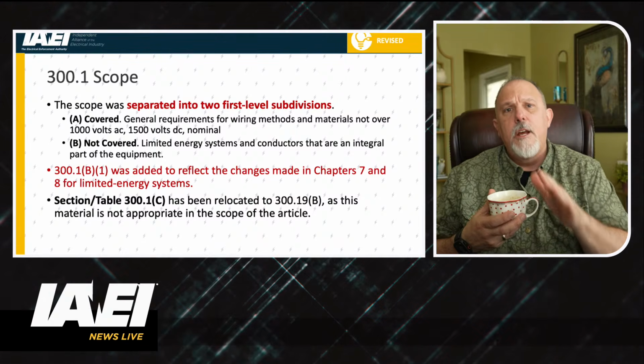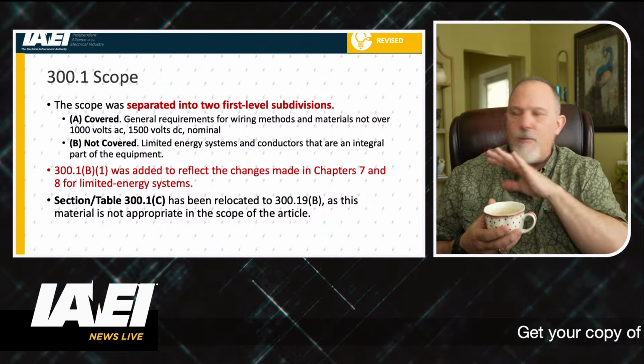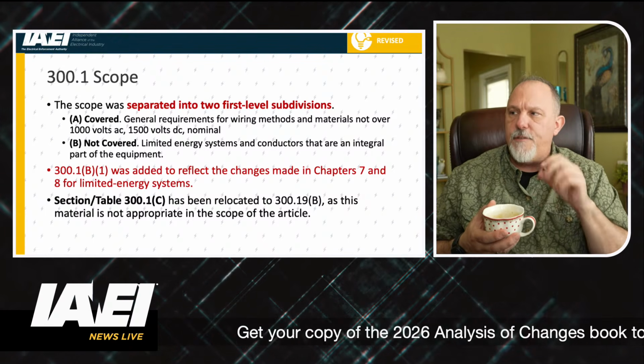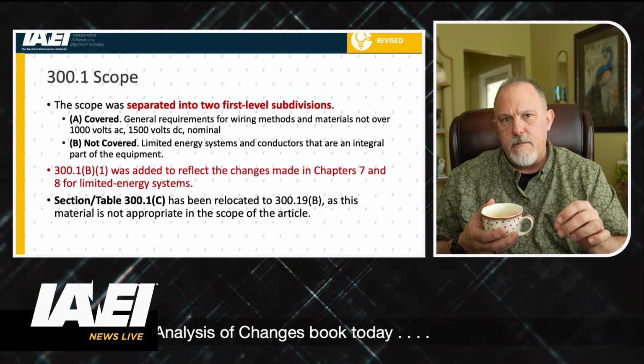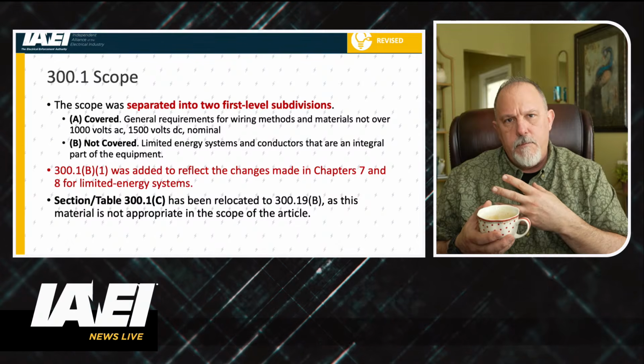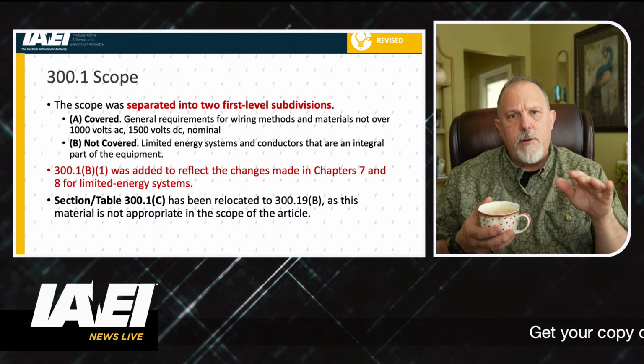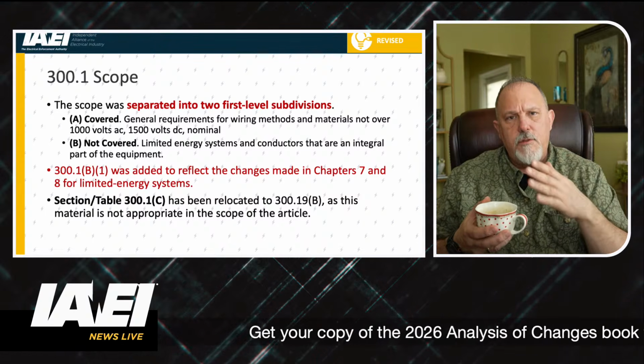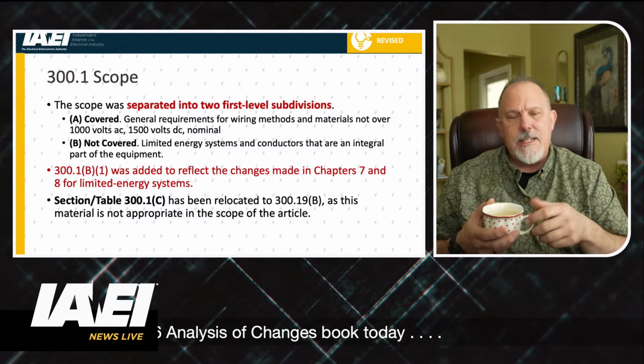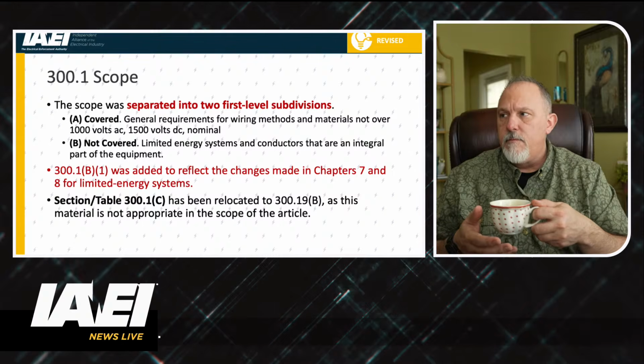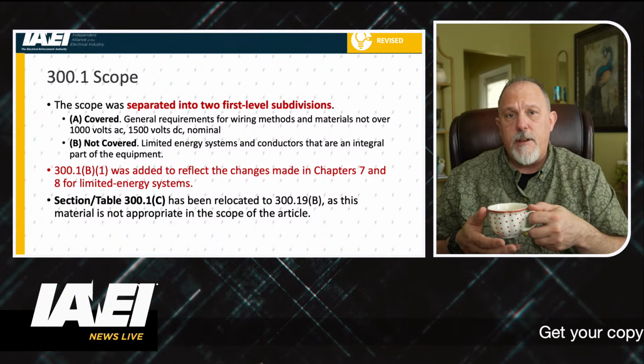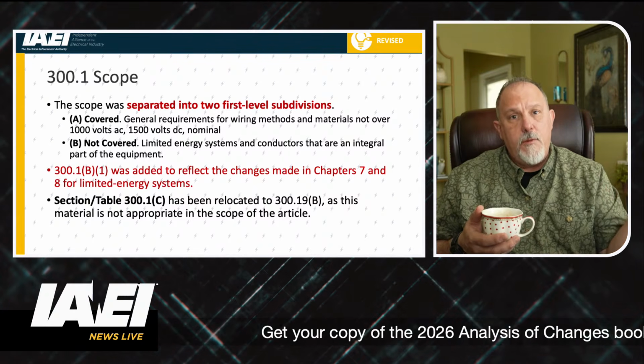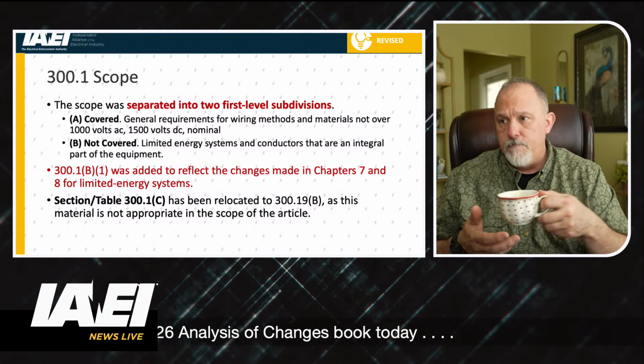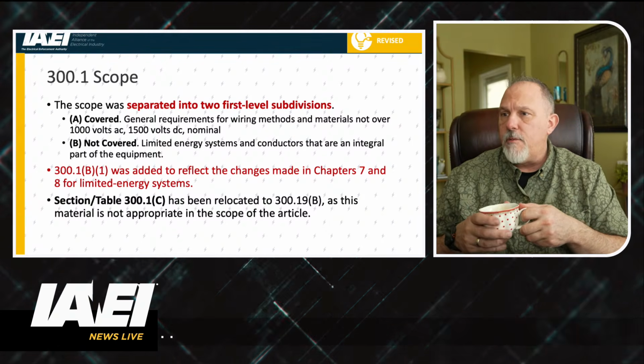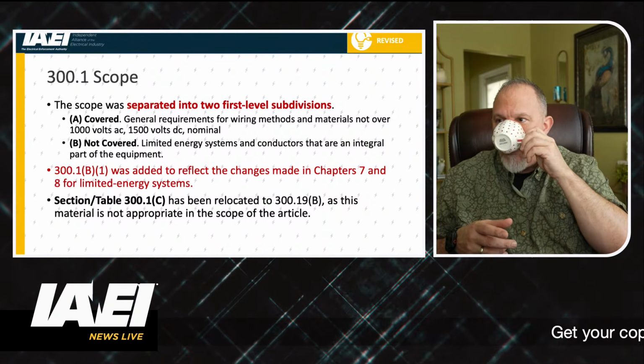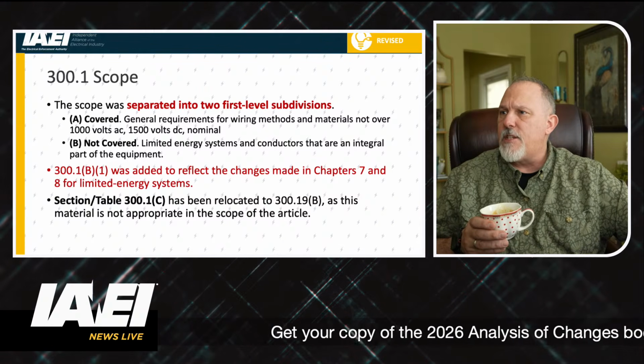I think my message there, the story is not we just moved this stuff. The story here is the fact that chapter 8 is no longer independent. They moved it into the rest of the book. The low voltage power or the power limited circuits are moved into chapter 7, and they had to put this exception in to say that these systems are now covered in Chapter 7, even though we've moved them from Chapter 8 into the rest of the book. Be mindful, they're not covered under Chapter 3, they're a Chapter 7 issue. So that's my story there, and I'm sticking to that.